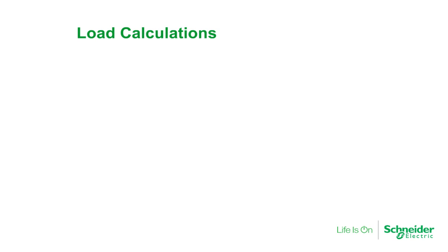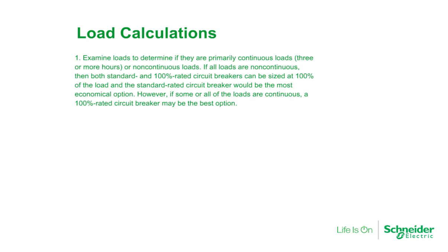When deciding to use standard or 100% rated circuit breakers, the solution is not always a clear-cut decision. The following steps will simplify making this decision. First, examine loads to determine if they are primarily continuous loads or non-continuous loads. If all loads are non-continuous, then both a standard and a 100% rated circuit breaker can be used at 100% of the load, and the standard circuit breaker would be the most economical option.